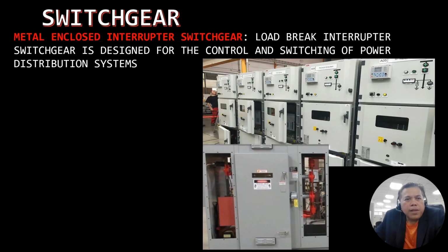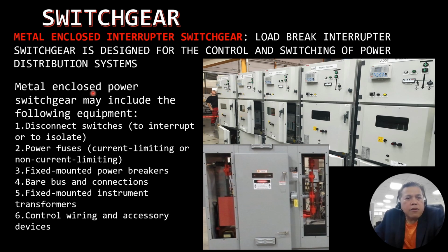So how about our metal enclosed interrupter switchgear? These are the photos you can see. This is the switchgear that we are usually utilizing at this moment in our project. Then metal enclosed power switchgear includes the following: disconnect switch, power fuses, as you can see, fixed mounted breaker, bare bus connection, fixed mounted instrument transformer, and control wiring.